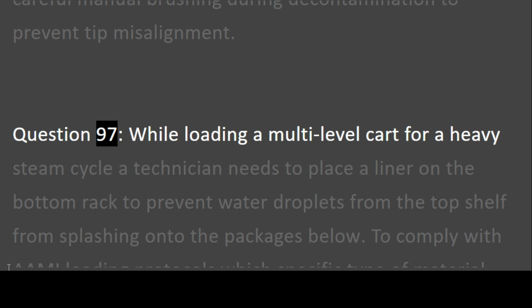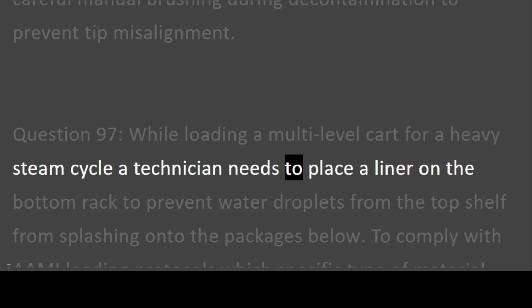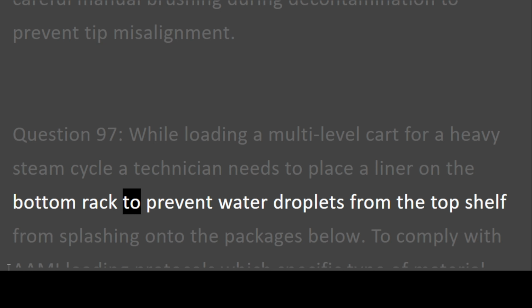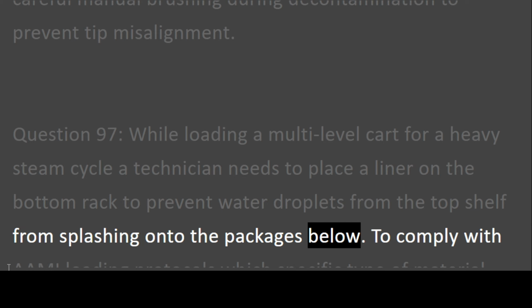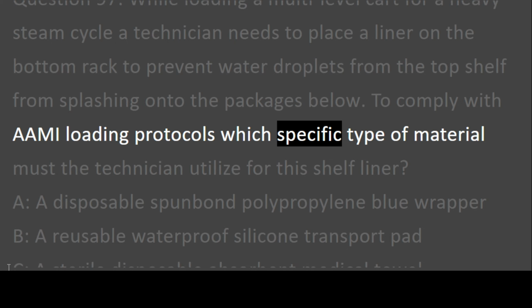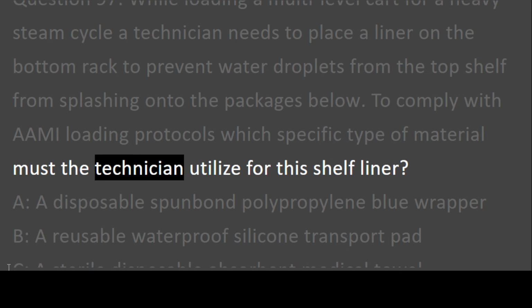Question 97. While loading a multi-level cart for a heavy steam cycle, a technician needs to place a liner on the bottom rack to prevent water droplets from the top shelf from splashing onto the packages below. To comply with AAMI loading protocols, which specific type of material must the technician utilize for this shelf liner?